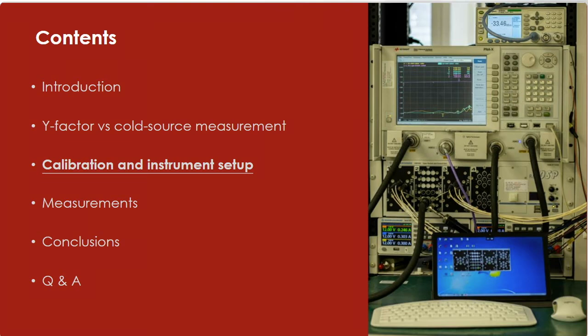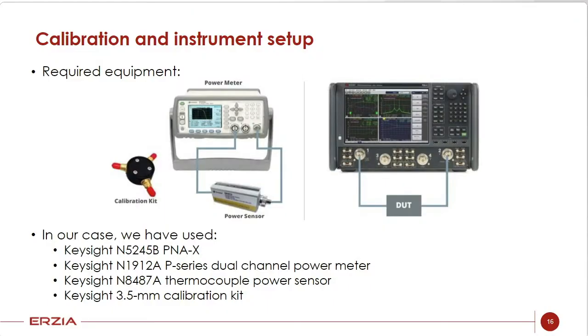Now we will present the calibration and the instrument setup. For the calibration, the required equipment is the calibration kit, the power meter, and the power sensors. Those are on the left graph. On the right side, we have the required equipment for the test itself. That's the PNA-X, for example, in our case, and of course, our device under test. We have listed the models we have used, but of course, you can use different models for the PNA-X, the power meter, the power sensor, and the calibration kit.